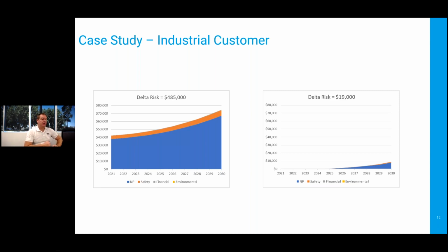To be honest, the best way of doing that now is through monitoring. There are lots of different styles of monitoring. We offer partial discharge monitoring for cables, permanent installation, and for switchgear. That monitoring solution will constantly record PD signatures, push that data to the cloud, and we have algorithms that run over the data and highlight anything of interest. We have trained staff who review the results daily and can alert customers when something's kicked off and there's a potential for a failure, so you get advance warning before one of these failures happens. That's usually more cost effective than sending people to walk kilometers of cable run every day or every week to check it.